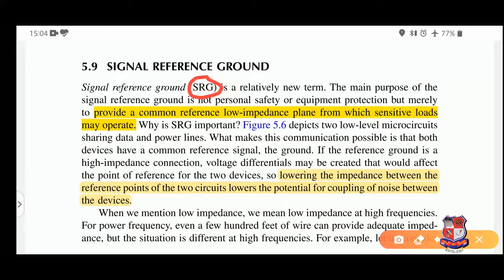The main purpose of the signal reference ground is not personal safety or equipment protection, but mostly to provide a common reference low-impedance plane from which sensitive loads may operate. The important word here is 'sensitive loads.' Unlike regular loads such as transformers, motors, and heavy machines, sensitive loads include communication equipment used mainly to transfer data.